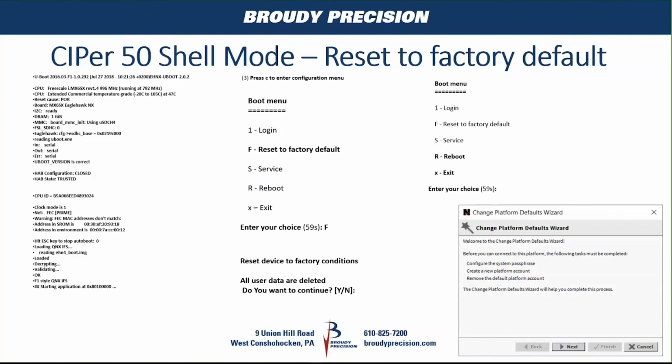And as I said, it blows away your station as well. So hopefully you can get in the station and do a backup from there so you don't lose everything. This doesn't have the same feature that an 8000 has, where you can go in and select menu item 8, where it would come up with an unlock code that we would send off to Tridium, and then they would send a code back that could be used to reset the platform and the credentials without touching the station or any of the modules that are installed. So with this, you got all or nothing.